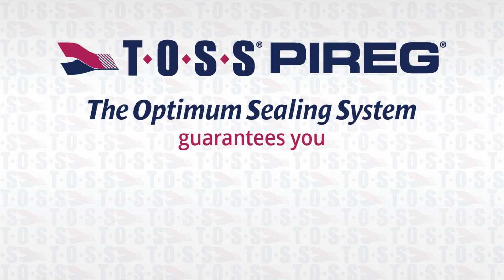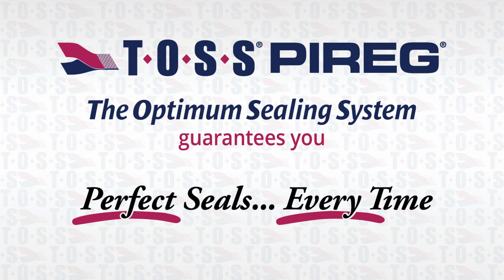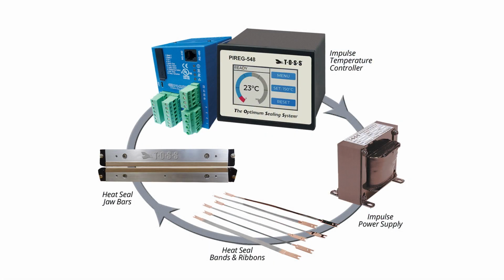TOSS technology came about as the highest evolution in impulse heat sealing controls and accomplishes this by using the heat seal band as a resistance temperature detector, also known as an RTD, that instantaneously reads the resistance of the heat seal band, which is equated to temperature, and is able to do this at 50 to 60 times per second. Let me start with a quick overview of the system and how it generally works. TOSS technology utilizes its PIREG brand heat seal controllers within a closed-loop system consisting of the PIREG controller, properly sized power transformer, current transformer, and seal bars or heat seal platen configuration.